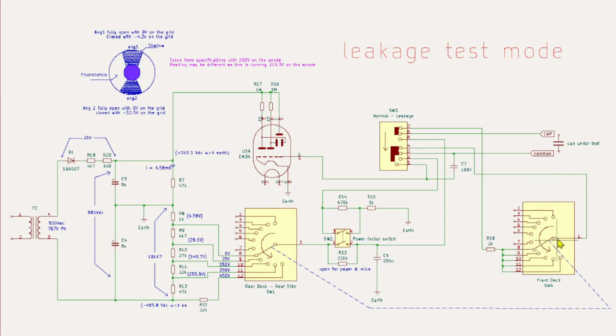And you can see that resistor is only really in circuit when it's in the leakage positions on the main switch. And so if we go back to this current path, if we've got it in the electrolytic setting, that switch will be closed and we'll have a 1k. And so it's quite easy from there with 1k to say that to fully close angle 2 you need 12.5 milliamps flowing through that resistor to earth, and to fully close angle 1 you need 4.2 milliamps flowing through that 1k resistor to close it. So it's expecting quite a few milliamps of leakage through that electrolytic capacitor.